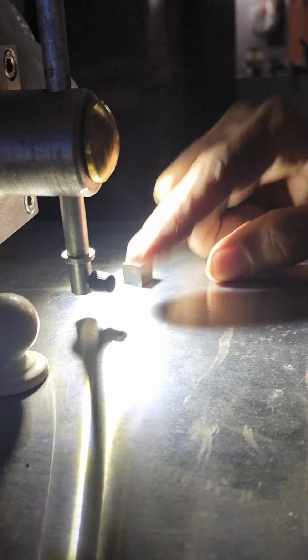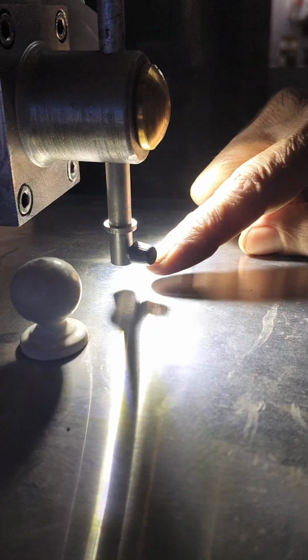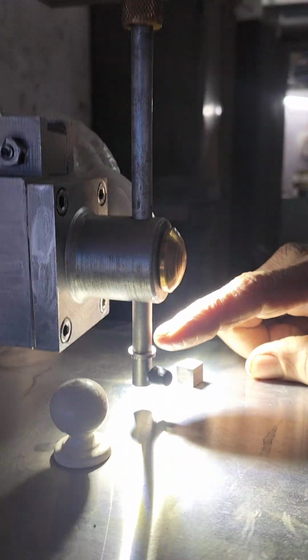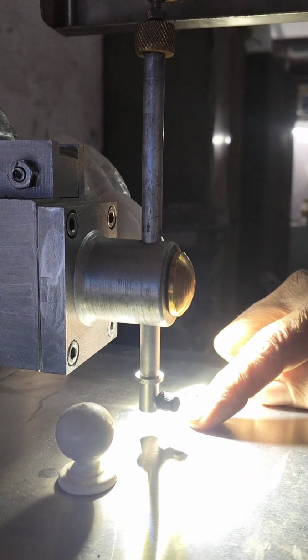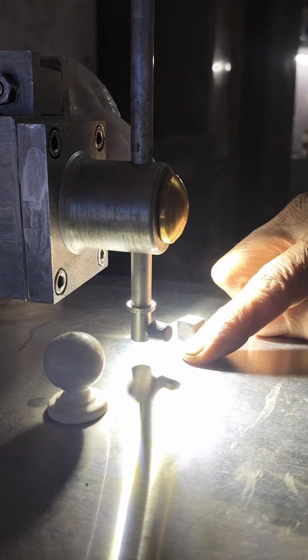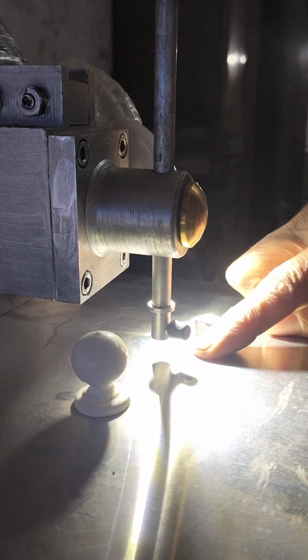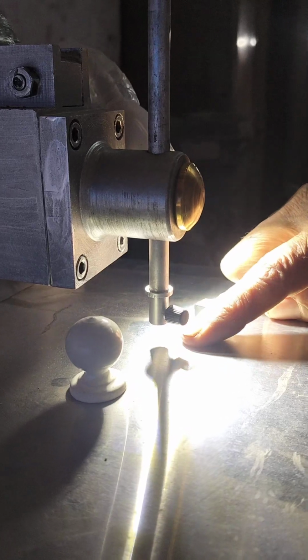Now whatever the distance of the block is, this is 10 mm. So naturally this plunger, when the timer is started, goes down. Of course this is a solid plate, so it won't go beyond that. So whatever distance is traveled is shown in the penetration reading. For that, now you have to do the reset.